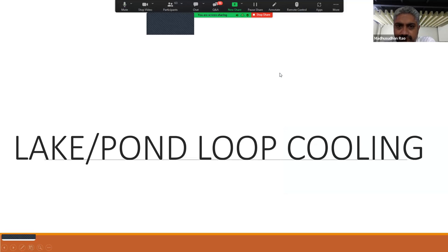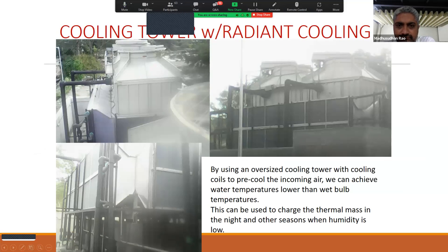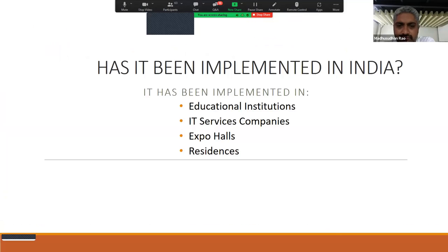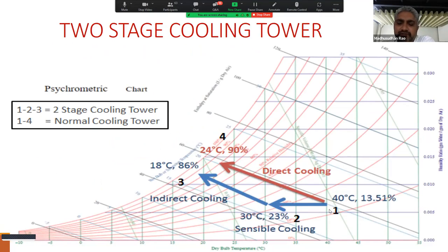Please explain double effect cooling tower. Okay, I'll go back to that and explain again. What will be the implication of ambient temperature, especially when ambient is high? Even if the ambient is high, let me go to that slide so that I can explain this. Yeah. So let's say you take a situation where it is 40 degrees centigrade, 13% RH. Extremely dry, right? Usually at 40 degrees centigrade we get 20%, but if you go along with me on this, this is just for demo, for explaining this.